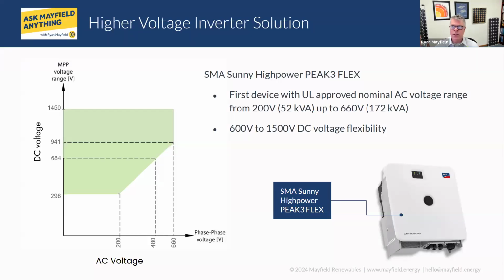What you get is naturally a reduced power output from that inverter. So yes, you can use these higher power or higher voltage inverters with an existing lower voltage input, but you'll have it at a reduced power output. I've seen where just limiting the power output of the inverter through programming is an acceptable solution to the utility, so you're not putting more power in. You replace a 50 kilowatt inverter with a 60 kilowatt inverter, but make that 60 kilowatt only produce 50. So you're able to meet that requirement.